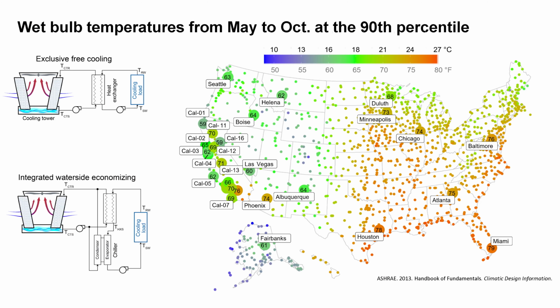And this is possible because wet bulb temperatures, which is an important parameter to design water side economizing systems, are a lot cooler during the night. So what you see in this plot is the wet bulb temperatures at the 90th percentile for the cooling season in many US cities. And depending on the climate, we can even do exclusive free cooling, where we just use the cooling tower, the water coming out of it, use the cool water to provide the cooling energy for our radiant systems.